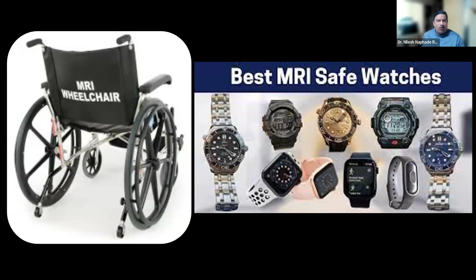What is MRI conditional? You can use that MRI conditional object in an MRI provided the conditions are fulfilled. It means you can use it with the 0.3 Tesla, not with the 3 Tesla. So those conditions if followed, that object is MR conditional. Look for these stickers on all the products that we use. There are MRI wheelchairs, and anesthesiologists amongst us who earn a living by working in NORA radiology, please buy these kind of watches. There are MRI safe watches available from all brands, including Casio and everybody. So you can have watches because if you're spending the larger part of your day in MRI rooms, there are MRI safe watches.